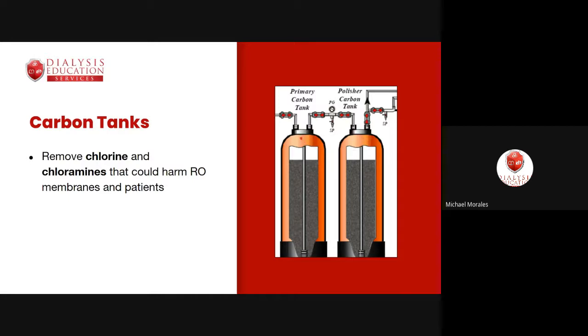Two carbon tanks must be installed in series with an empty bed contact time of at least 10 minutes — meaning the water must take at least 10 minutes from entering the first tank to exiting the second. The tanks contain granular activated carbon (GAC), an extremely porous burned organic material. One teaspoon of GAC can have the surface area of a football field, giving it enormous capacity to adsorb chlorine and chloramine.